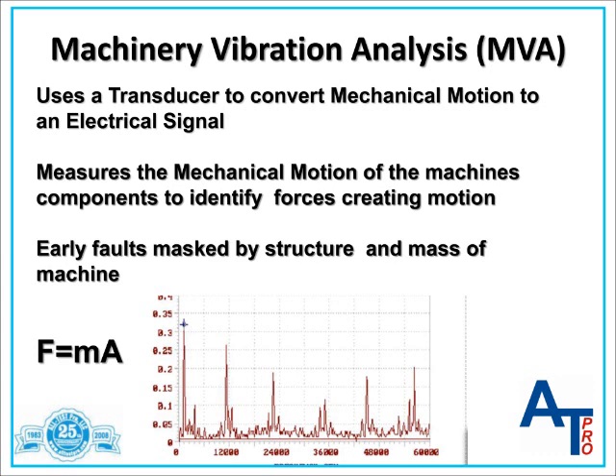The vibration instrument performs a fast Fourier transform on the transducer signal to determine the frequencies of the measured forces. Therefore, with MVA, the ability to identify developing faults is limited by the machine's design, mass, and structure. Many developing faults may be buried in the background of the machine's normal operation, or the developing fault forces may be insufficient to move the bearing support or other parts of the machine that are being measured.